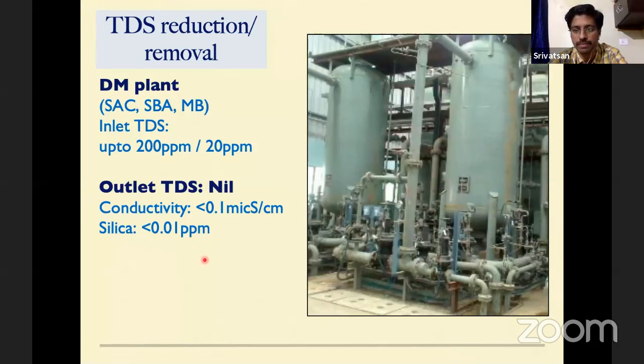0.01 ppm. Once these resins get exhausted, that is to the maximum possible level, it has absorbed all the salts. We need to stop the system. We need to regenerate the system using acid and alkali to remove all the adsorbed salts present in it, so that it can be utilized. It will be ready for the next cycle of demineralization. This process is called demineralization system.